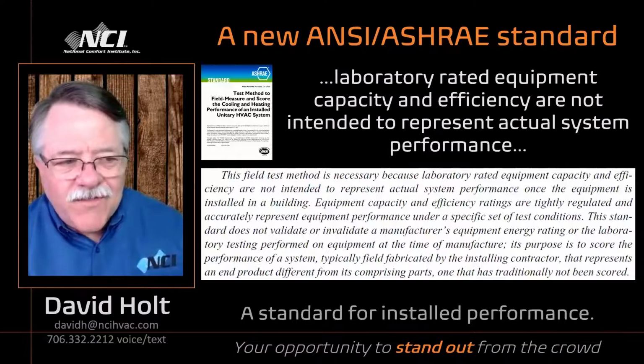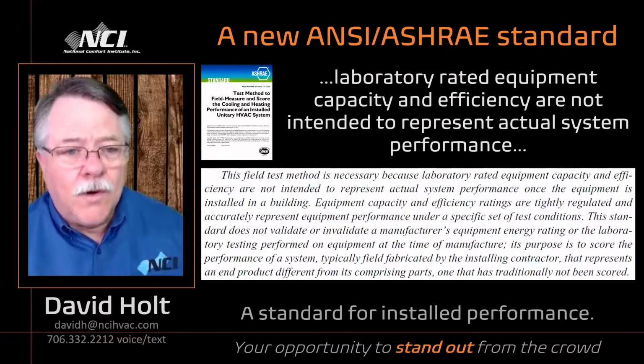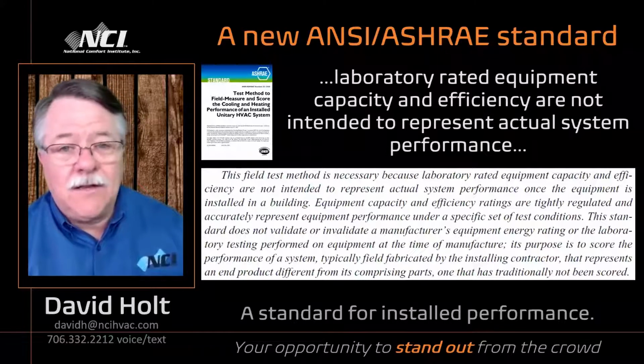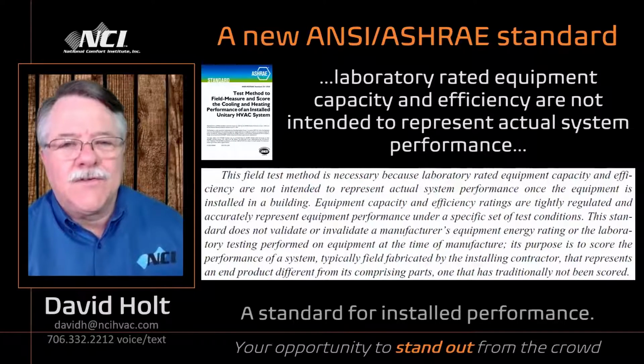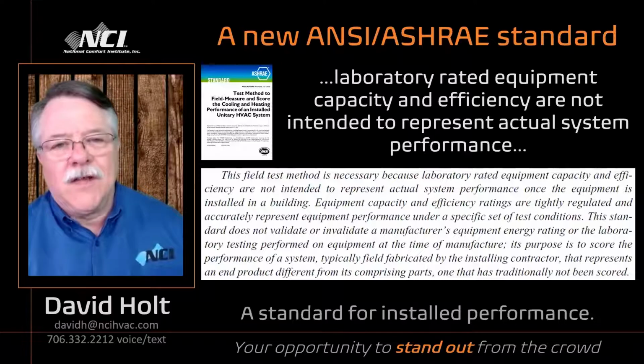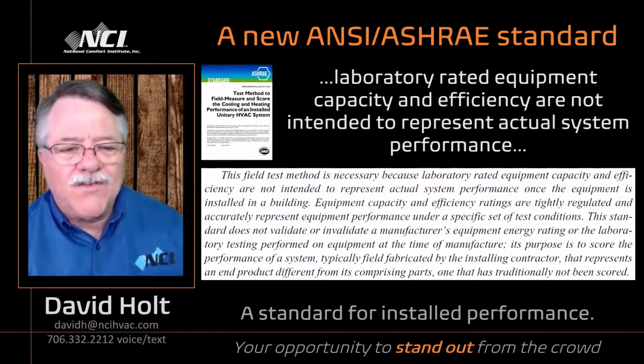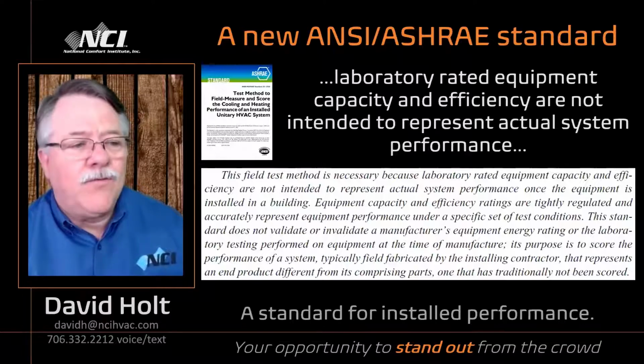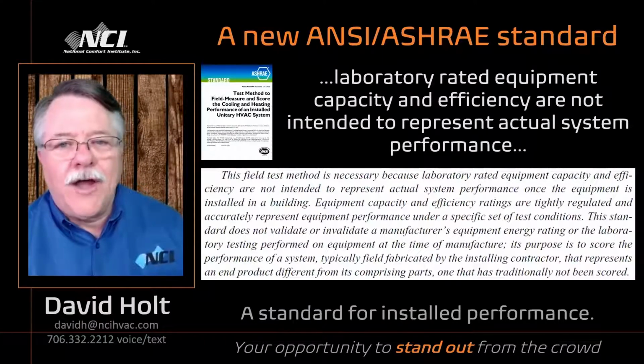So this field test method is necessary because laboratory rated equipment capacity and efficiency are not intended, they never have been intended, to represent actual system performance once the equipment is installed in a building. It's never been intended to say, this is how it's going to operate in the building. This is how it operates in a lab. Equipment capacity and efficiency ratings are tightly regulated and accurately represent equipment performance under a specific set of test conditions. So we're not saying, and certainly ASHRAE is not saying by this standard, that the current SEER, AFUE, HSPF rating system is flawed. Far from it. We completely endorse those rating systems.